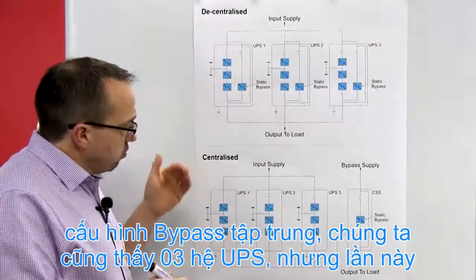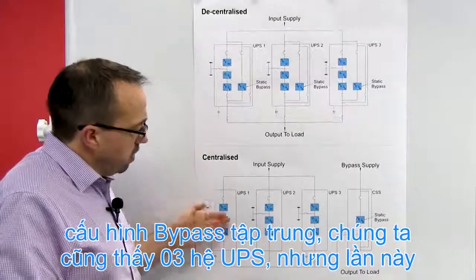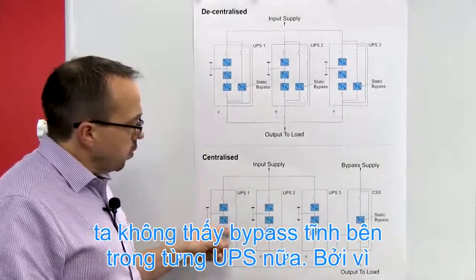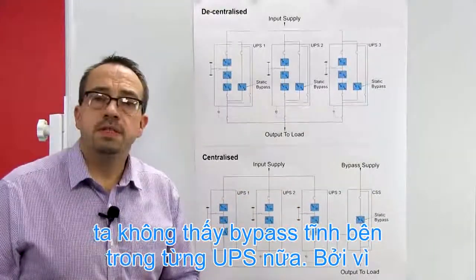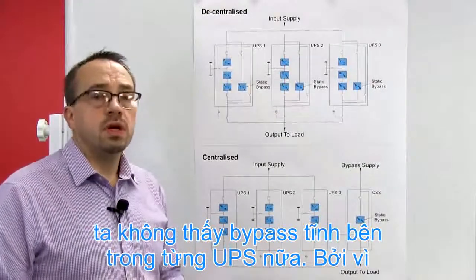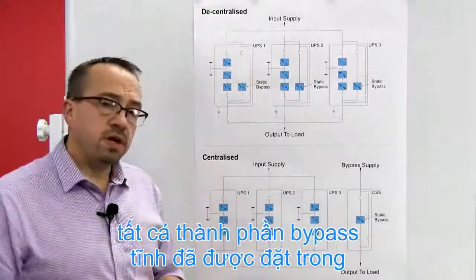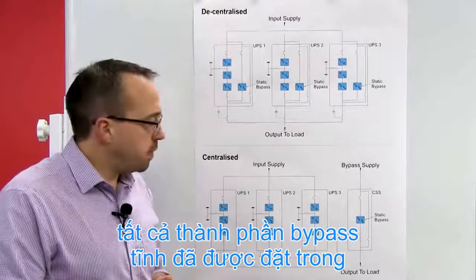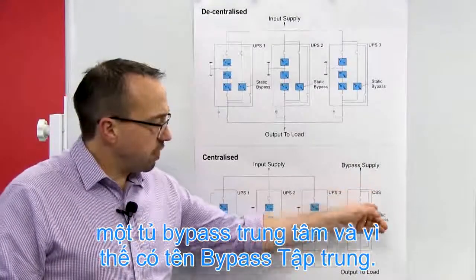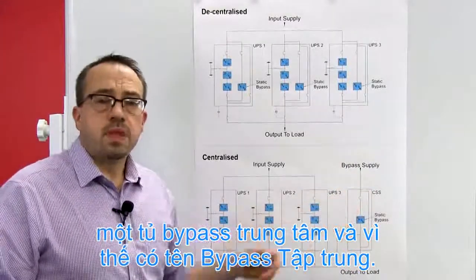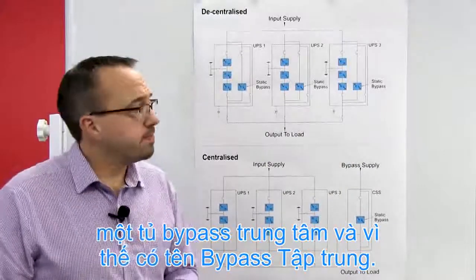However, if we look at the centralized system, we again have the same three UPS systems, albeit this time we don't have any static bypasses within the UPS modules, and therefore because it is a centralized system, all of the static bypass components are located in a centralized bypass cabinet, and hence the term centralized.